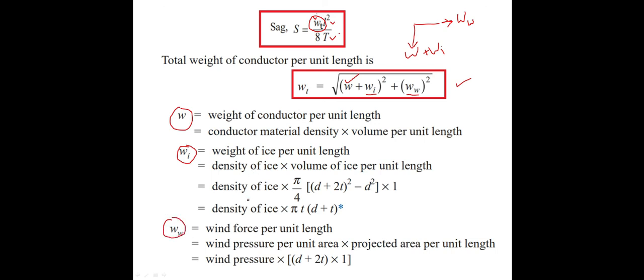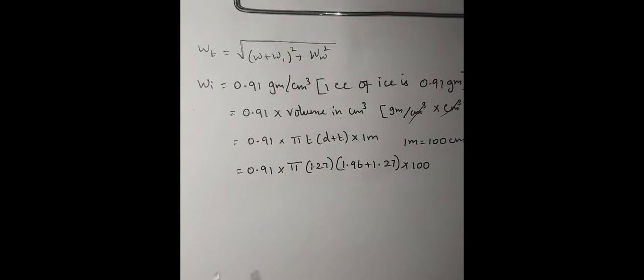Density of ice is given. Using the volume formula, Wi = 0.91 × π × t × (d + t) × 1 meter. The formula for wind force per unit length is: Ww = wind pressure × (d + 2t) × 1. In both cases, the length of 1 meter is substituted. The weight of ice is 0.91 gram per centimeter cube, and we must substitute the volume in centimeter cubes.